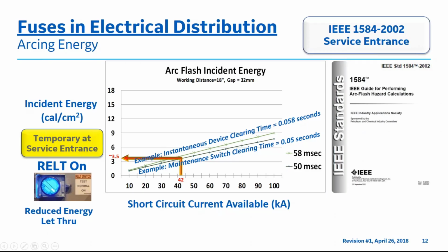The GE HPC2 device with the maintenance mode turned on meets the 2017 NEC requirement per 240.67(B)(2), which clears an arcing fault within 0.05 seconds. Again, this is a temporary feature with Class L fuses at a service entrance location.